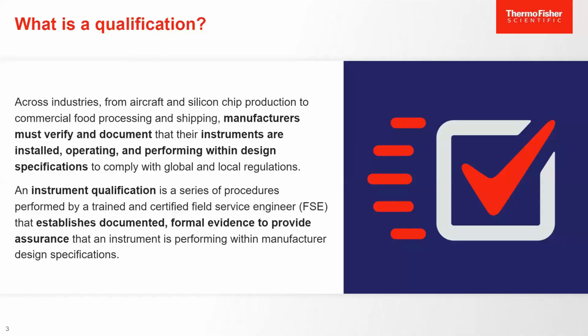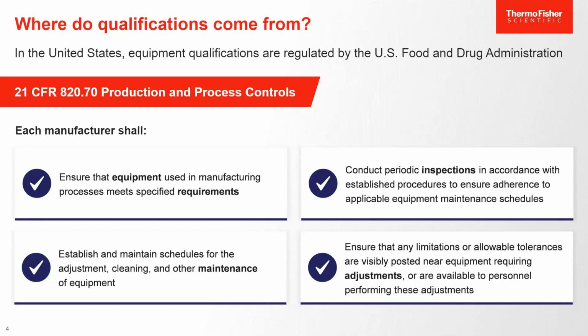What is a qualification? Across industries, from aircraft to silicon chip production to commercial food processing and shipping, manufacturers must verify and document that their instruments are installed, operating, and performing within design specifications to comply with global and local regulations. An instrument qualification is a series of procedures performed by a trained and certified field service engineer, FSE, that establishes documented formal evidence to provide assurance that the instrument is performing within manufacturer design specifications.